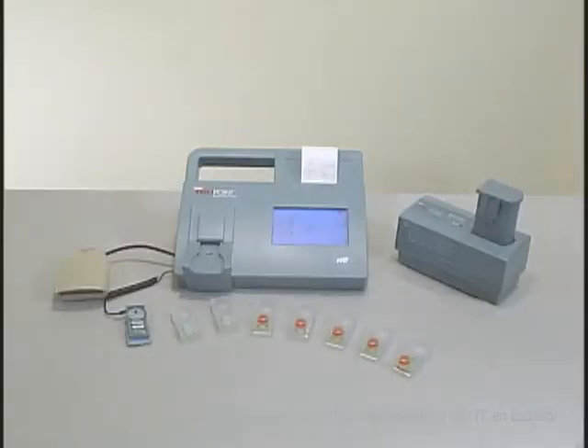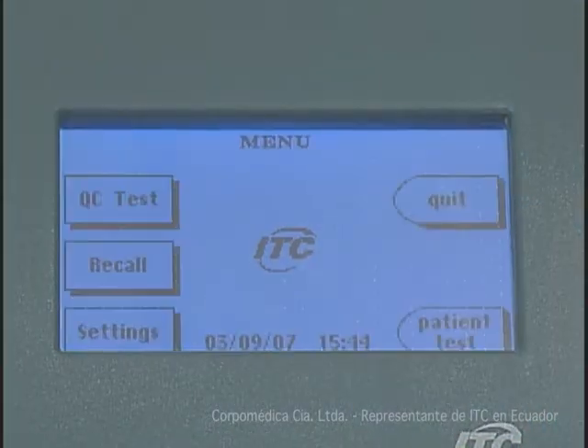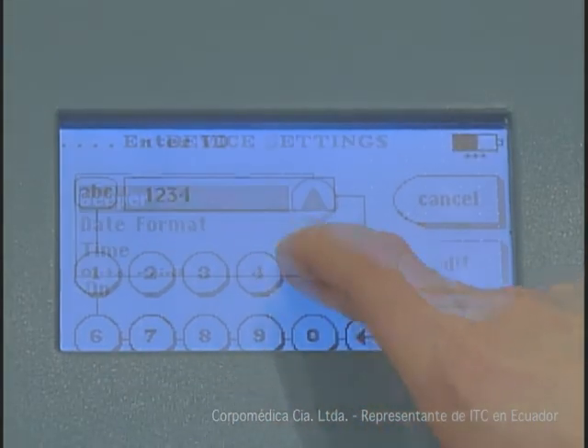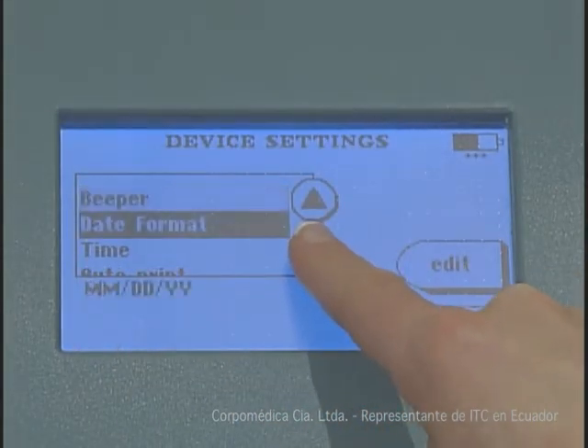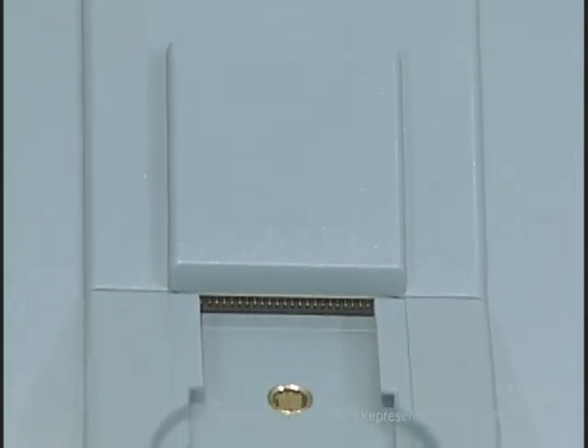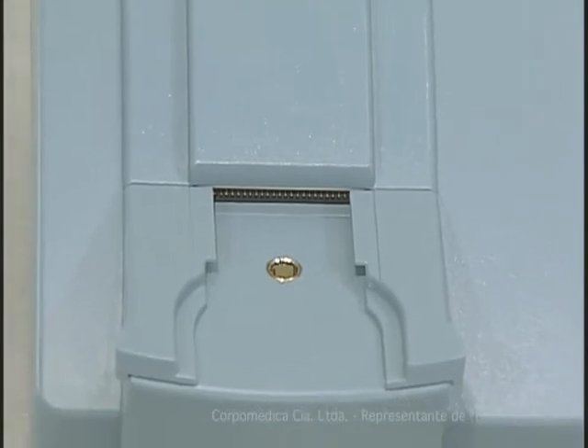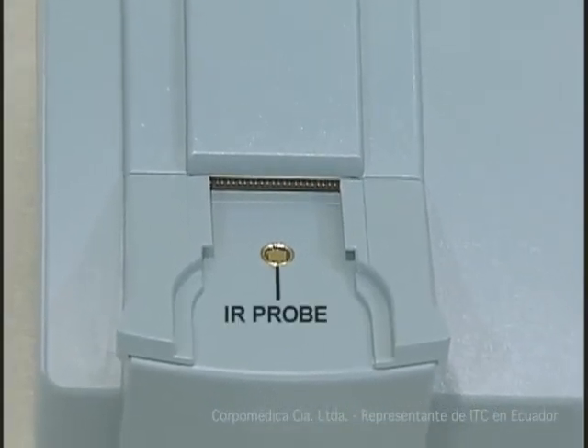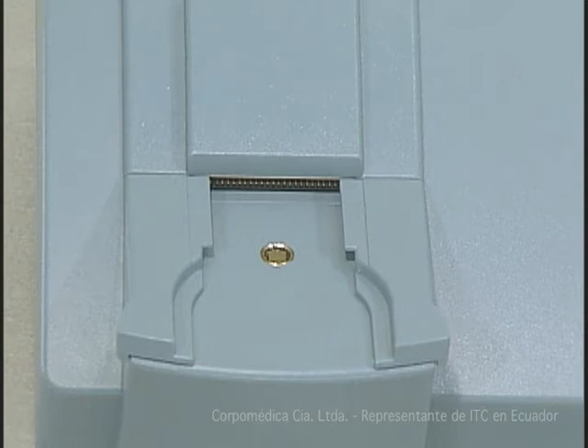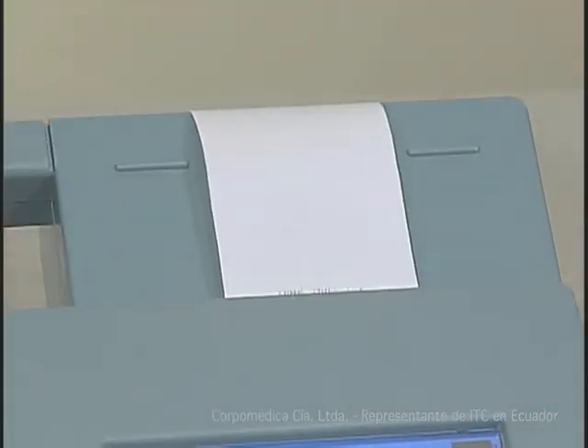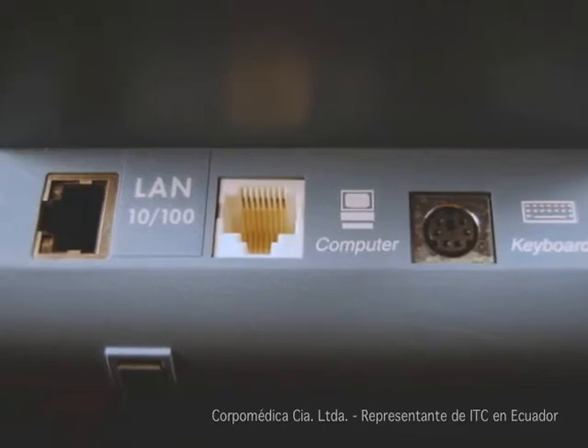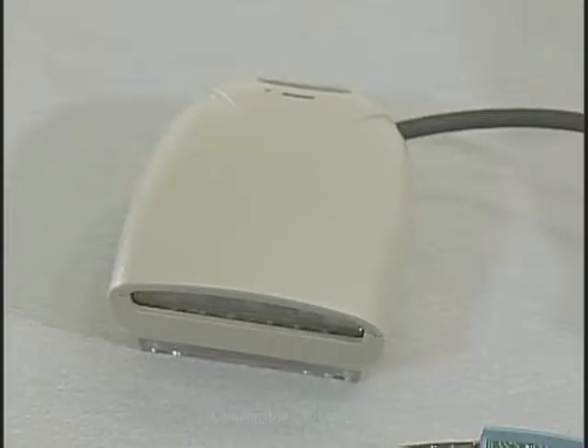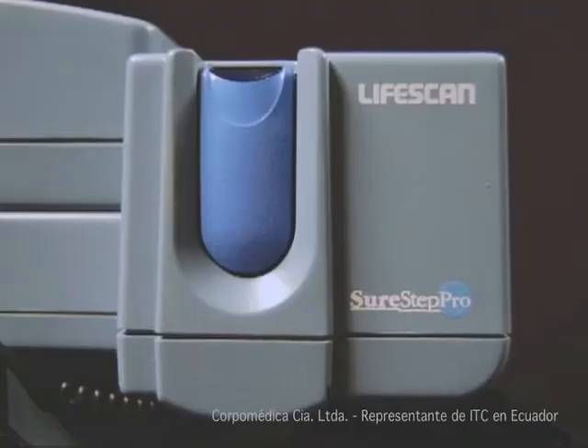The IRMA TruPoint system is easy to use and includes the blood analysis system and the battery charging system. An interactive touchscreen easily guides the user through all aspects of operation. You can enter information and select analyzer options by pressing the touch-sensitive keys. The testing platform consists of an edge connector block which electronically connects the disposable cartridge to the analyzer. The IR probe monitors cartridge temperature. The sample is heated through the edge connector via a heater circuit. An integrated printer provides a hard copy of test results and information. The TruPoint provides a serial port and Ethernet connection. Optional components include a barcode scanner and the SureStep glucose module.